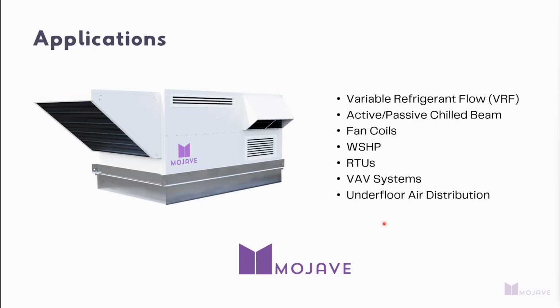decoupling latent when you leverage low dew point, which is an interesting and newish industry trend where some engineers are looking at pulling latent load off of VRF systems or chilled beam systems or rooftop systems. And what that is, you're designing around a dry coil and basically condensing no moisture on that sensible system, making it a sensible only system.